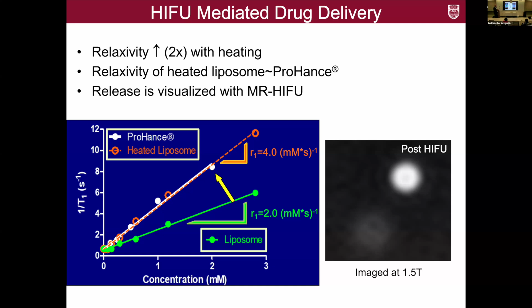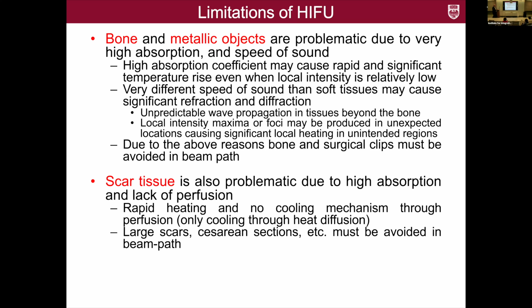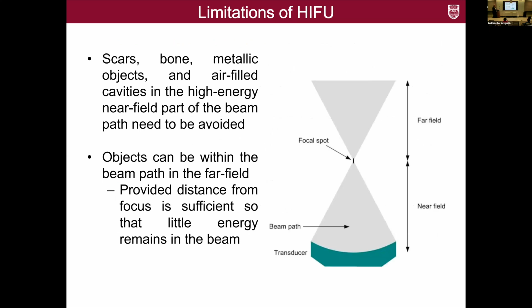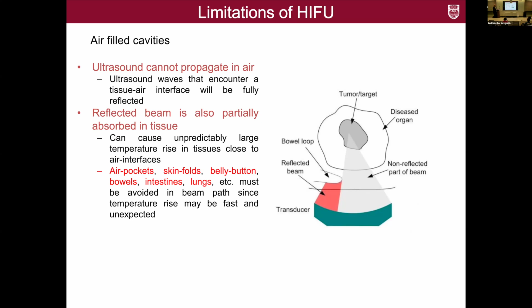Jump over that. There's of course, at the very end, I want to show you some limitations. We have problems with HIFU as we have in diagnostic ultrasound, especially when there are bones, metallic objects like implants, air spaces, scar tissue. So we have to consider this all in our calculations and treatment modifications before we start scanning the patient. So ultrasound cannot propagate in air, you know that already maybe from other studies, but the reflected beam is also a problem. So we have to be careful because if there are air bubbles, if there's metal, then you might see some reflections that damage the tissue in the area.